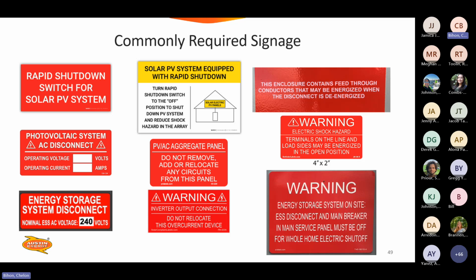Inverter output connection. Do not relocate this overcurrent device. Then, this enclosure contains feed-through conductors that may be energized when the disconnect is de-energized. That would be a supply side connection. Could be many different connections to an existing service. Warning, electric shock hazard. I can hardly read these. Then last one, warning, energy storage system on site, ESS disconnect and main breaker in main service panel must be off for whole home electric shutoff.